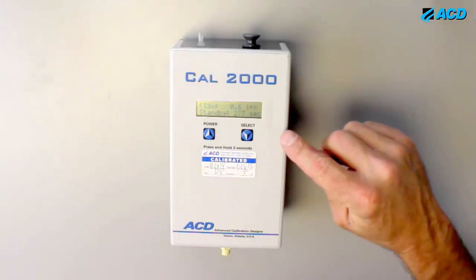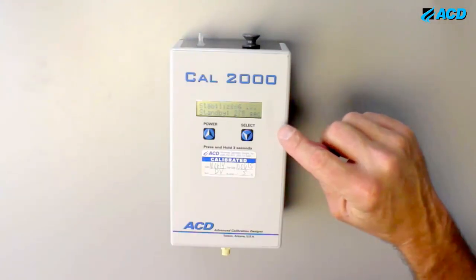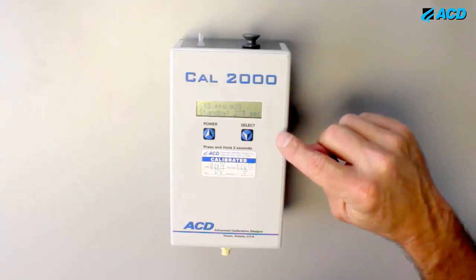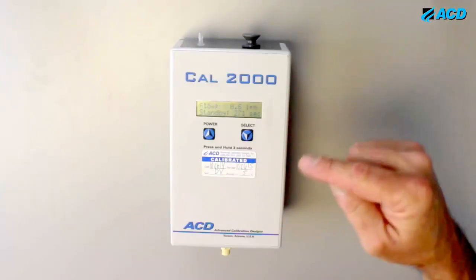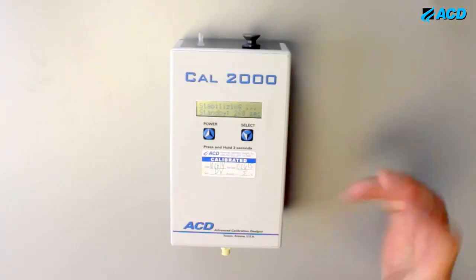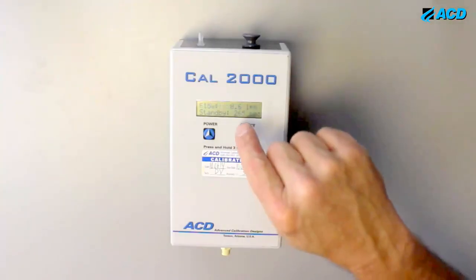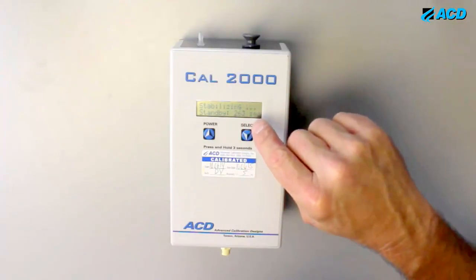The last time I used this, it was flowing at 0.6 liters per minute and 15 parts per million. Because it's an electrochemical generator, the first time you turn it on, it has to stabilize for 5 minutes, and you see that it's counting down from 300 seconds, okay?